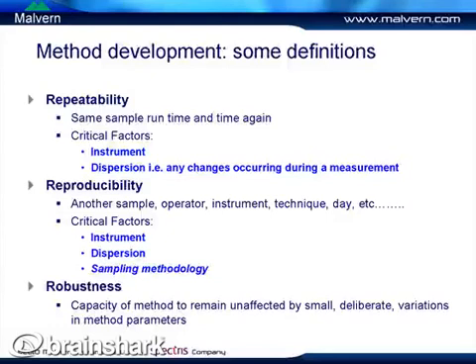Secondly, we're going to look at reproducibility. This is a slightly more challenging test, as it covers measurements carried out on more than one sample, operator, or instrument. So as well as testing the instrument and the state of dispersion, we're also testing the sampling method — how the sample is extracted from your bulk material.